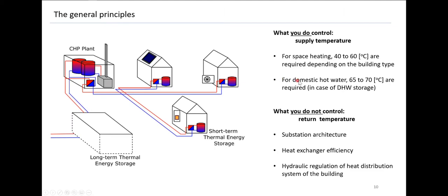What do we ultimately need in buildings? For space heating, between 40 and 60 degrees depending on the building type and redistribution system — radiators or low-temperature heating makes a difference. For domestic hot water, we need higher levels if we have a storage tank due to legionella issues. But what you do not control as an operator is the return temperature. Each substation gives you back whatever it returns — if one gives back 75 degrees, you cannot do much. What influences this return temperature can be the substation architecture, the efficiency of heat exchangers, and the hydraulic regulation of the building's heat distribution system.